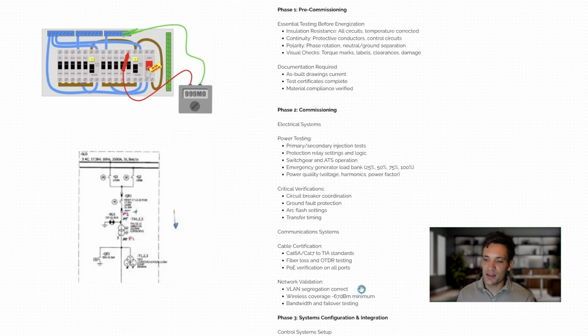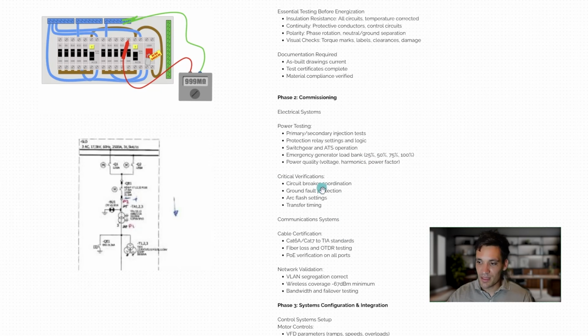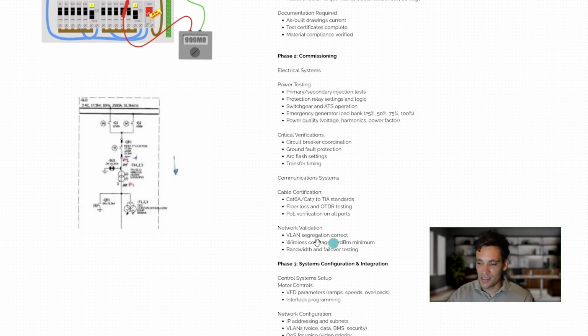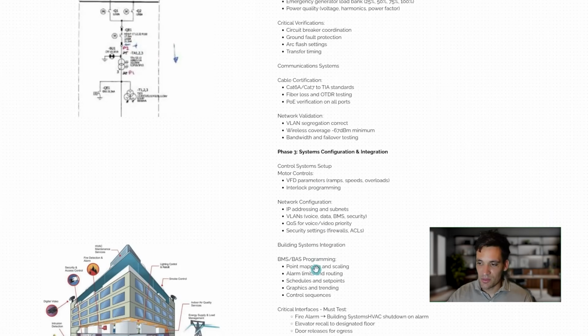So commissioning is all about checking that what we've installed, what the design has designed, is meeting the original requirements. So we do things like secondary system injection tests to check things are working correctly. We look at protection relay settings, make sure everything's operating. We test that, for example, if we have an emergency backup power supply, that the automatic transfer switch operates. We might do load bank testing on our generator, measure power quality. Basically, we want to verify that circuit breakers are coordinating, that there's ground fault protection, arc flash settings, transfer timing, all these things are configured correctly. We'll do the same thing for our communication system.